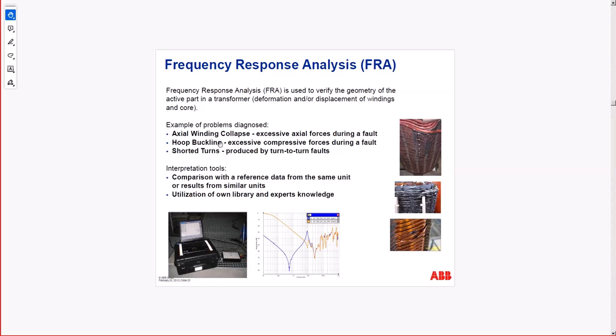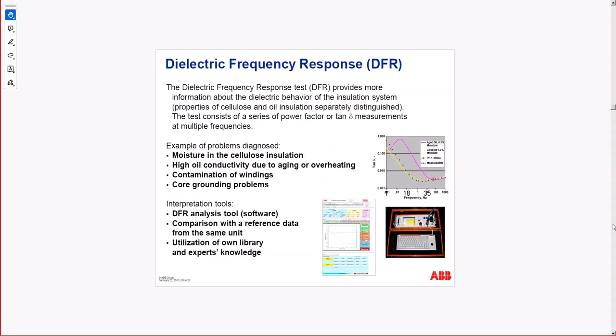So, an example of a problem: axial winding collapse. You see here in the picture on the right hoop buckling, excessive compressive force during a fault, and shorted turns at the bottom. Those are the typical outcomes of degradation. Interpretation compared to the reference, have your own trend and library. That's very important for the system engineers.